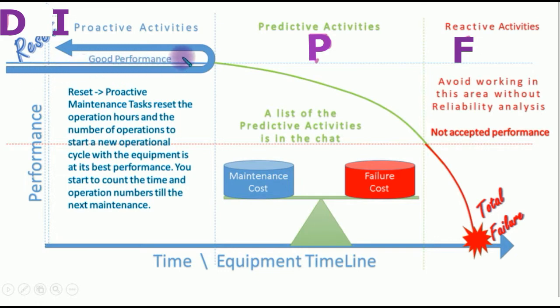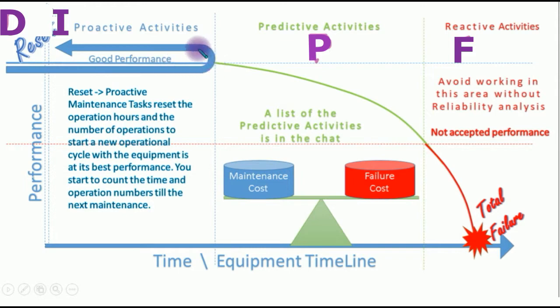During this time, when you do some activities, that's proactive activities, and most of the time it's based on time and/or number of operations. Usually, you like to take the time and/or the number of operations to work in this area before going to any potential failure, and then you reset to best performance again. The criticality about working like this is that the maintenance cost is very high.